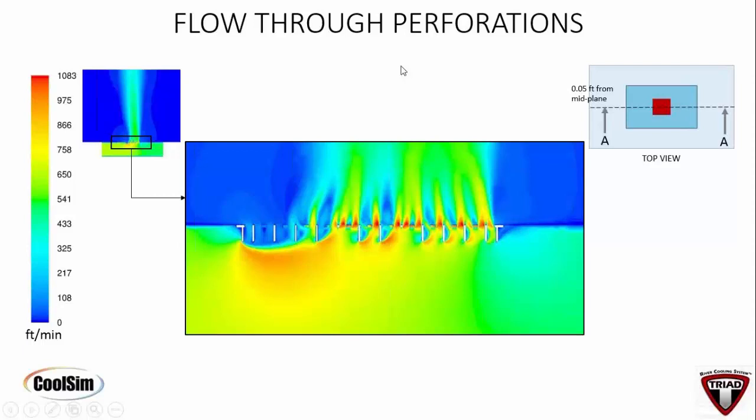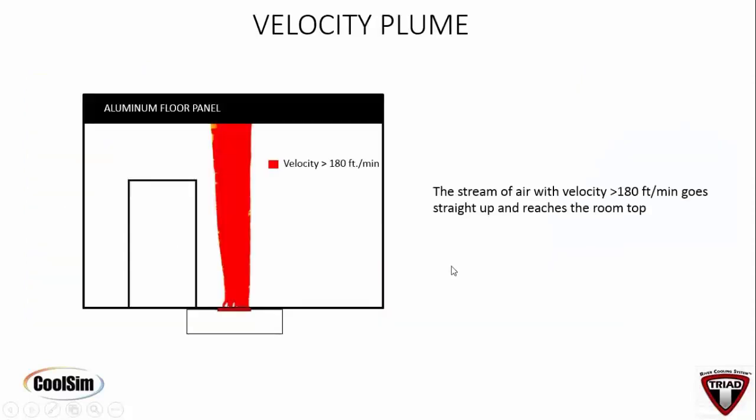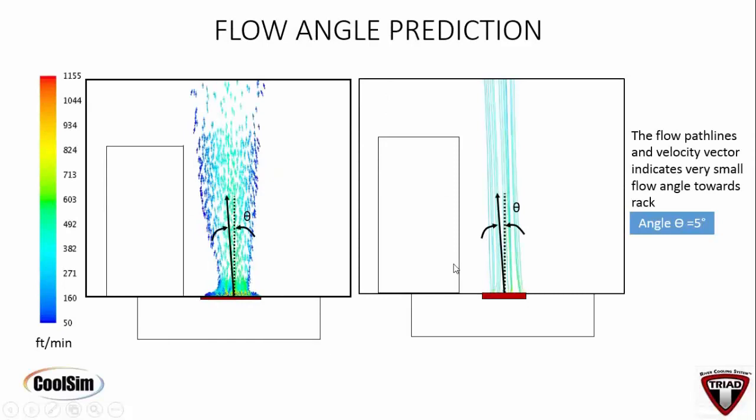So if you've got a ceiling plenum return or even a conventional convective return on your CRAC unit, it's going to put cold air back into that thing. It doesn't send it through the rack. So not a good comparison to the triad tile. And it has no angle at all. The angle's less than 5 degrees, or 5 degrees or less.